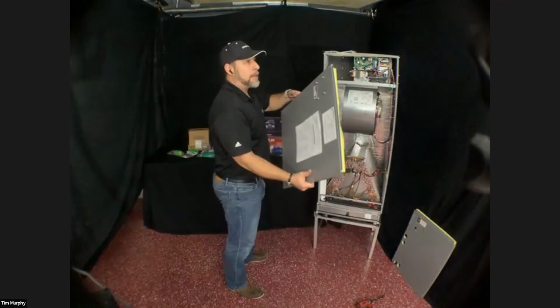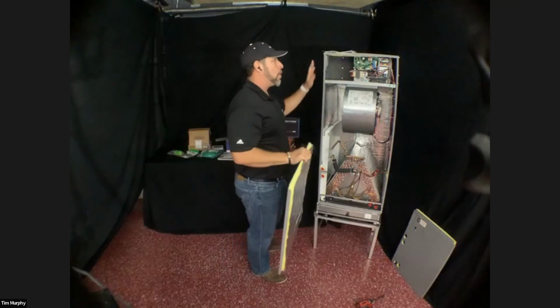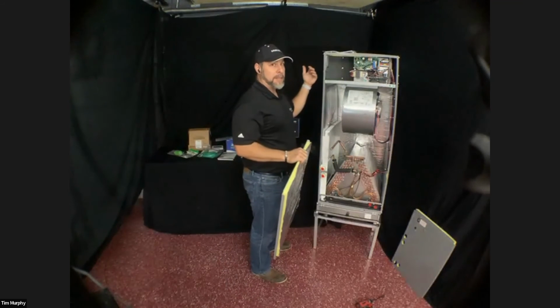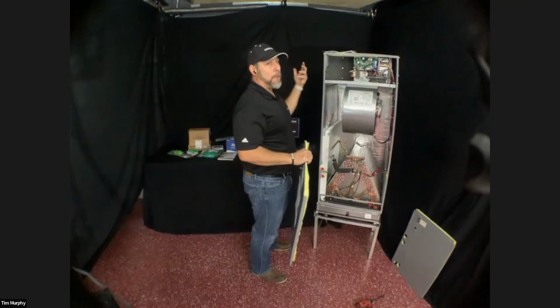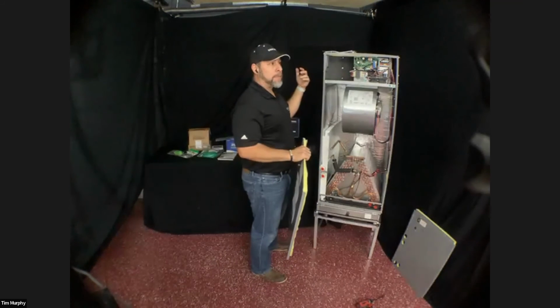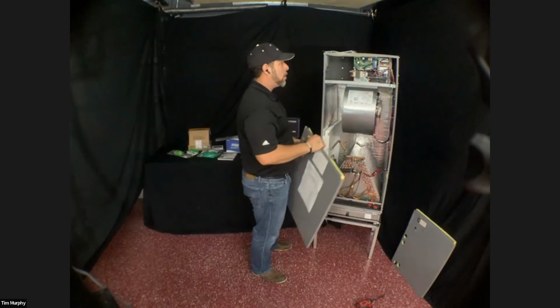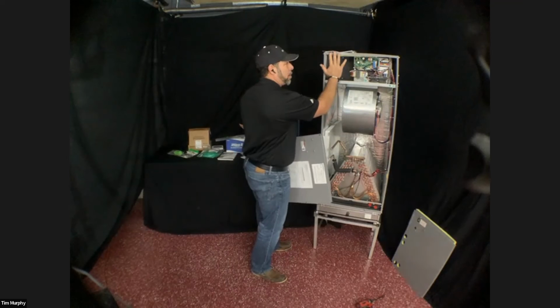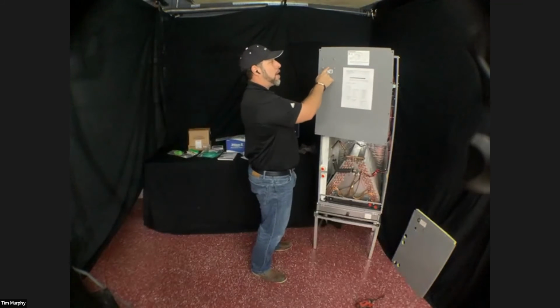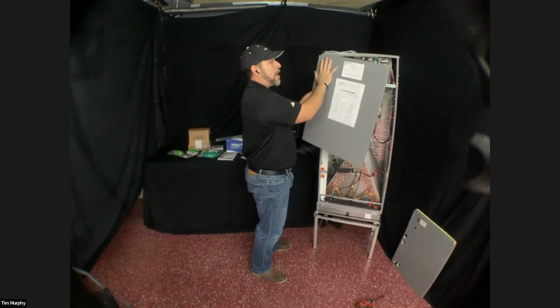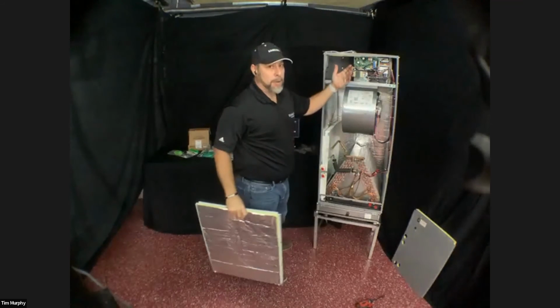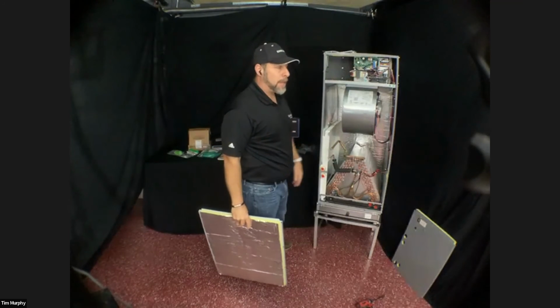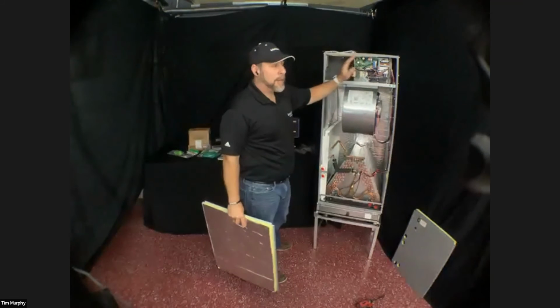That would be a situation where if you're going back behind a standard HVAC changeout, then you would want to utilize that existing line voltage that was powering the air handler. But when you get the heat kit, it's going to come with a breaker that goes right there, and if you see there's a little cutout here already, you take these screws out and now you would power it. Then it's very similar to a standard heat kit, you just plug it into this board, and it'll control it.